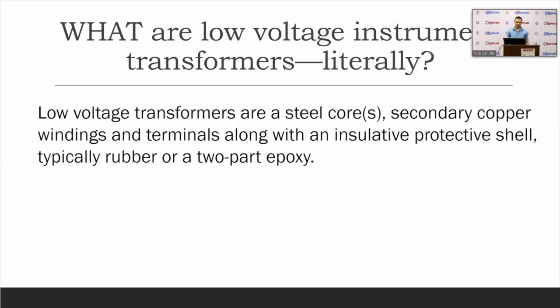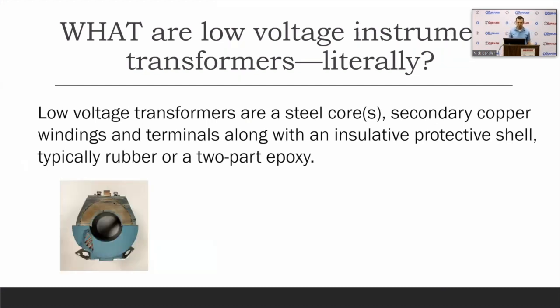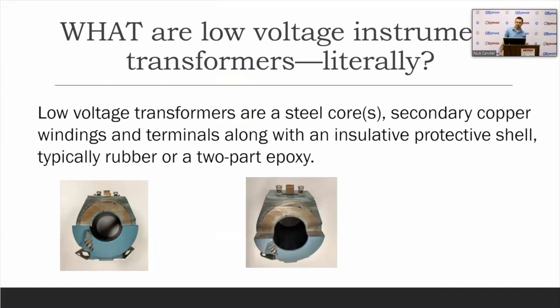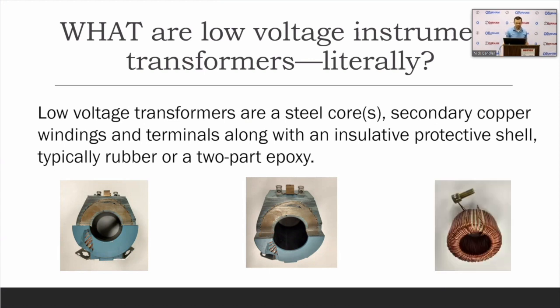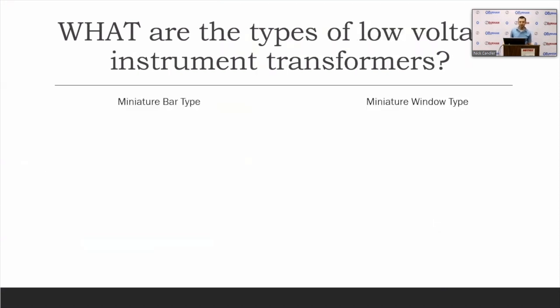But what are low voltage instrument transformers literally? So these are going to be a steel core. There's a couple different material types for that. The silicon magnetic core steel is historically what the industry used, but migrating to more extended range and some high accuracy transformers are using a paper thin nanocrystalline material for that core. So that's going to be your secondary windings and terminals along with an insulated product. A lot of manufacturers out there will use a rubber encapsulation. The GEC Durham uses a two-part epoxy. We'll see some benefits to that epoxy later, but that's essentially the materials of an instrument transformer.